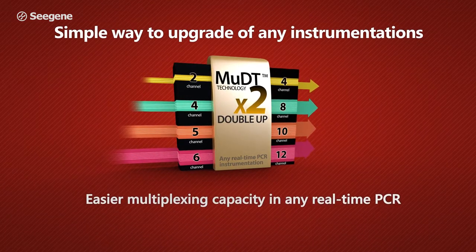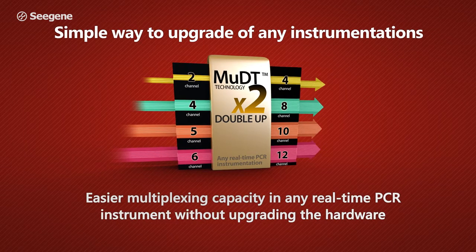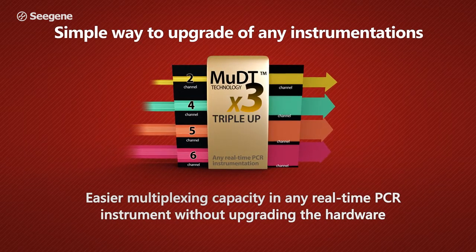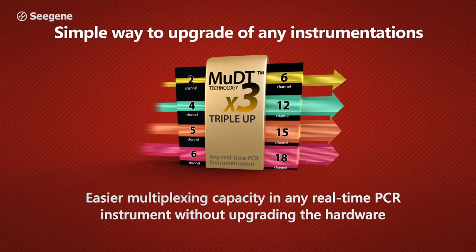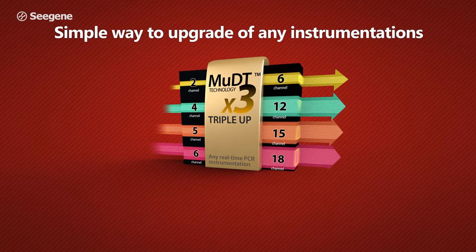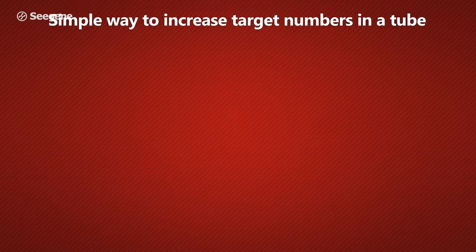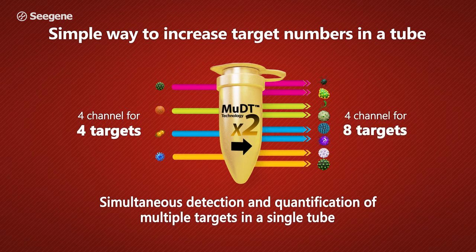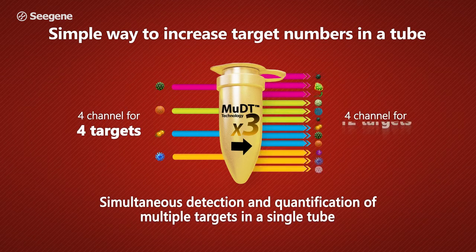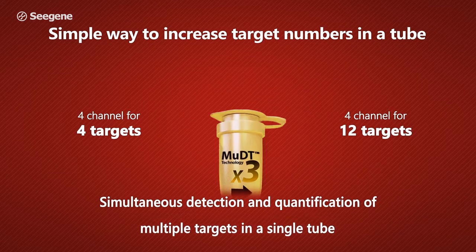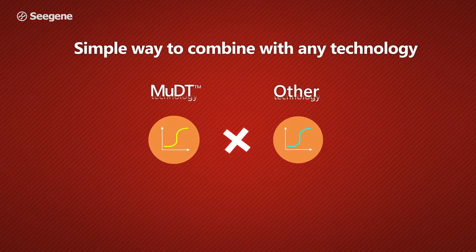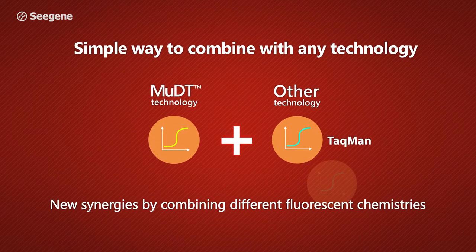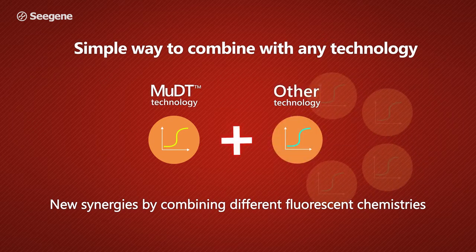MUDT increases the multiplexing capability of any existing real-time PCR instrument without requiring new hardware. It increases the number of targets per tube up to three times while still providing superior quantitative CT information. MUDT works with any fluorescent chemistry, opening new possibilities for the molecular diagnostic industry.